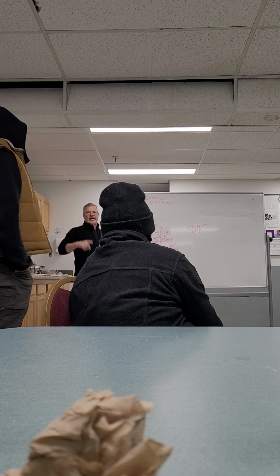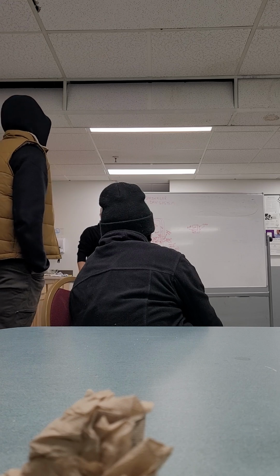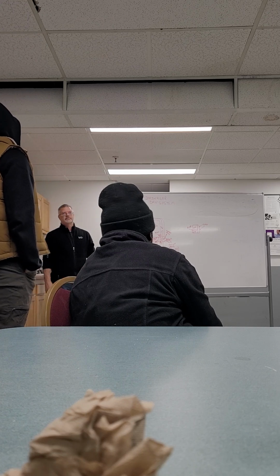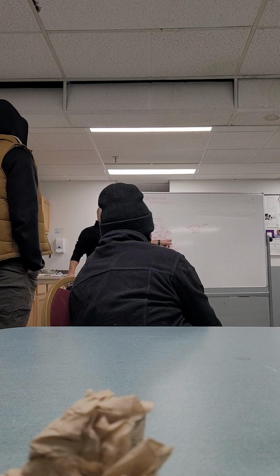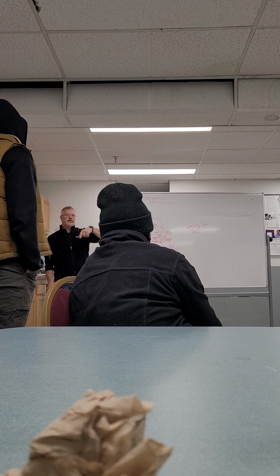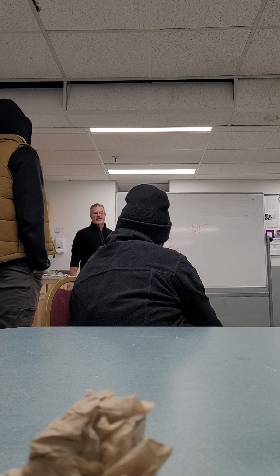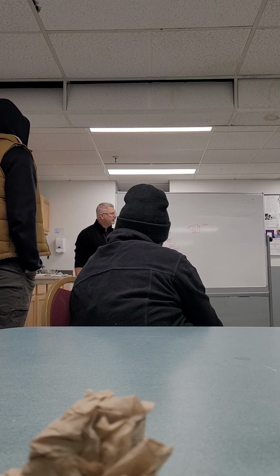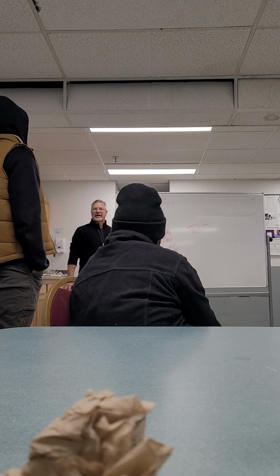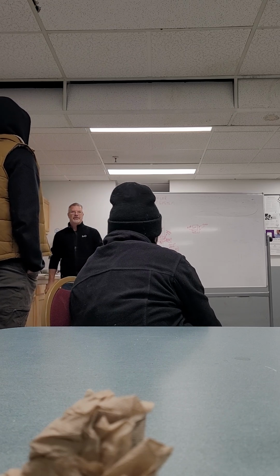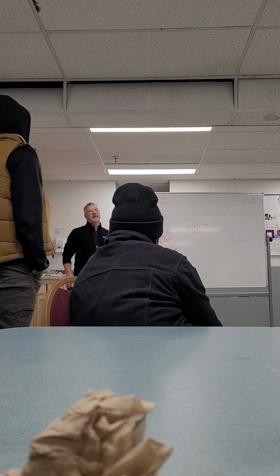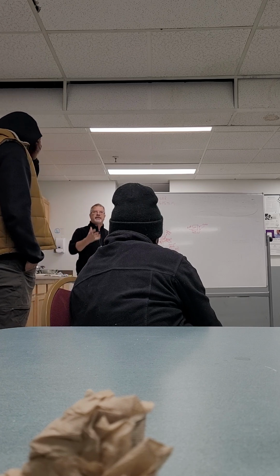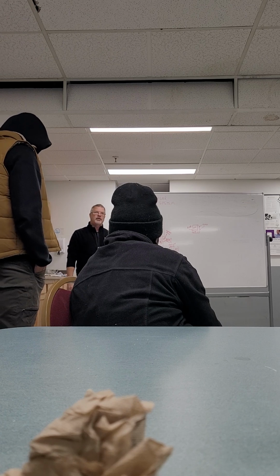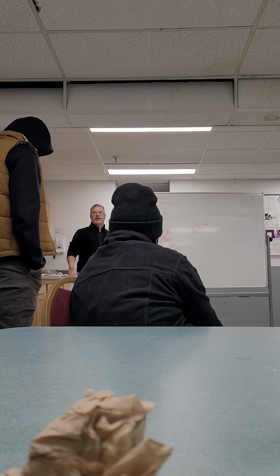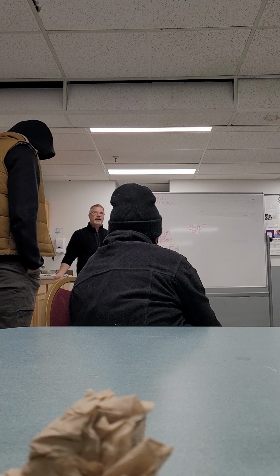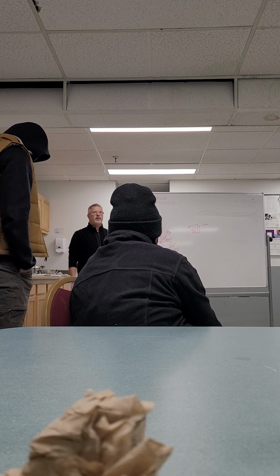It will also tell you tamper. Everybody know what a tamper is? Tamper alarm: if somebody goes and turns this valve, it goes to the fire alarm panel, and it tells security that somebody is actually closing a valve. So if you guys aren't working on the system and somebody's playing with the valve, they're tampering with it, and that's what the alarm will be. It'll be a tamper alarm that somebody's closing that valve. So if you see that on the fire alarm panel, it'll tell you exactly where it is.